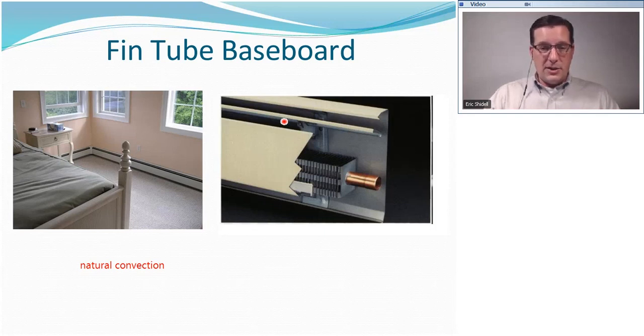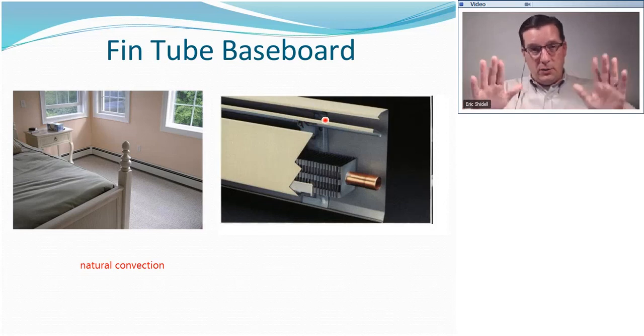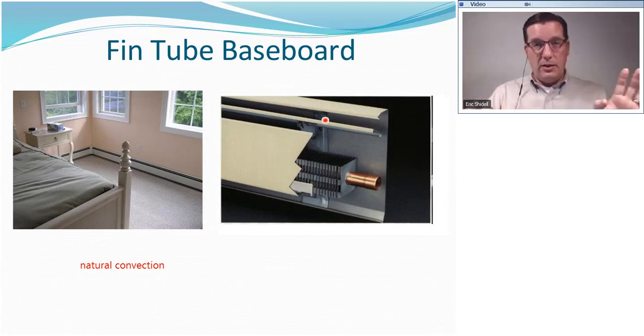There's this little flapper right here, which can turn it on or turn it off. When it's closed, we don't get that airflow, and the radiator or the baseboard is essentially off. So those need to be kept open. The bottoms need to be kept clear. So if this is in a children's room, for example, and they're packing dirty clothes under the radiator or toys are falling up under there, that can prevent that natural convection of air flowing through the baseboard.